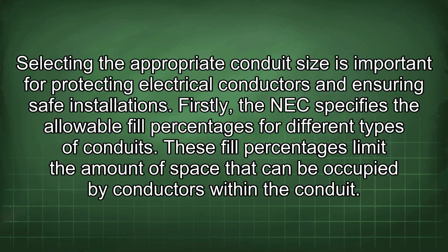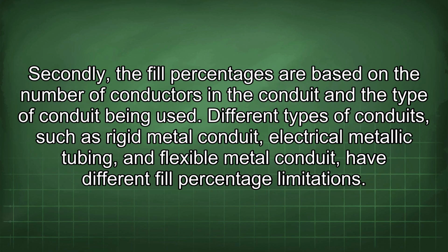Selecting the appropriate conduit size is important for protecting electrical conductors and ensuring safe installations. Firstly, the NEC specifies the allowable fill percentages for different types of conduits. These fill percentages limit the amount of space that can be occupied by conductors within the conduit. Secondly, the fill percentages are based on the number of conductors in the conduit and the type of conduit being used.